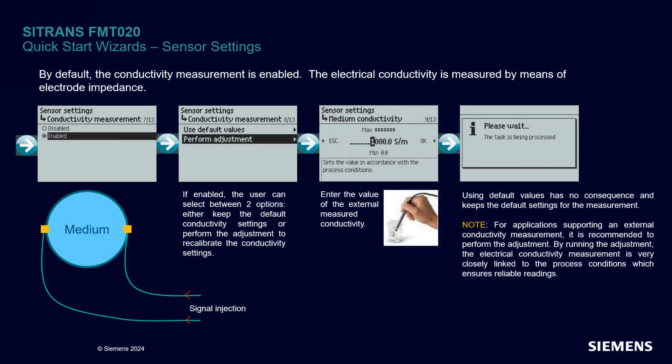The FMT-020 offers a new feature in the measurement of electrical conductivity. It is enabled by default. You can optimize its performance by entering the conductivity of the medium if you know it. With conductivity as a new process value, you can monitor the mixture of material in your pipe based on its conductivity property.